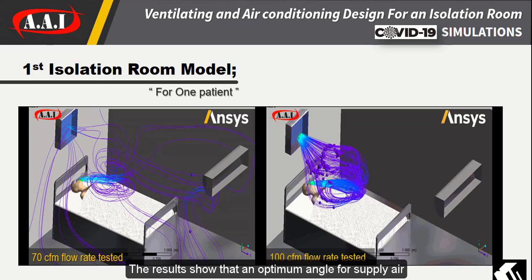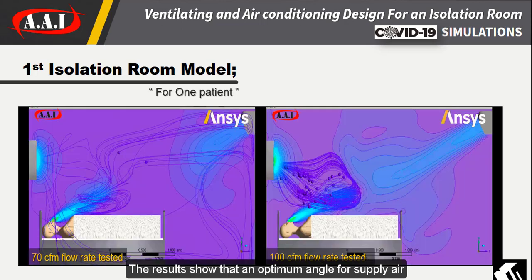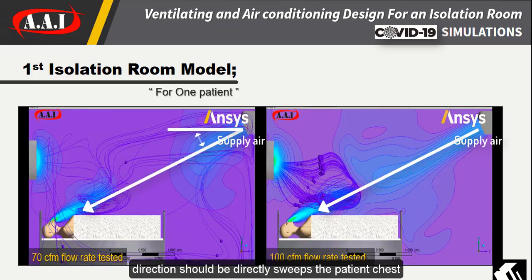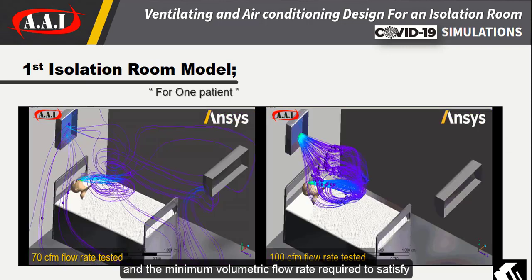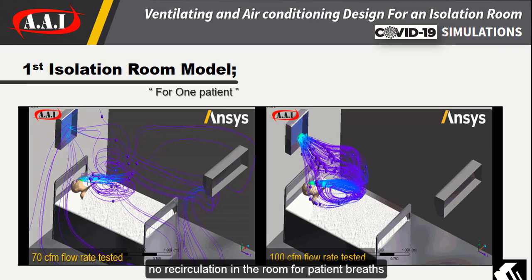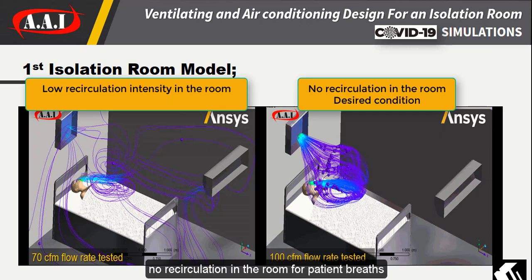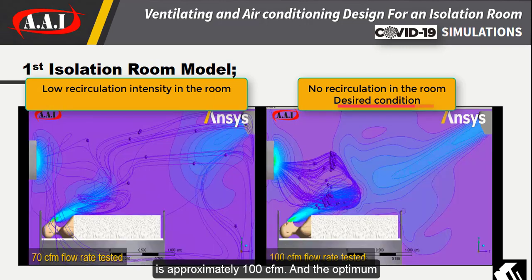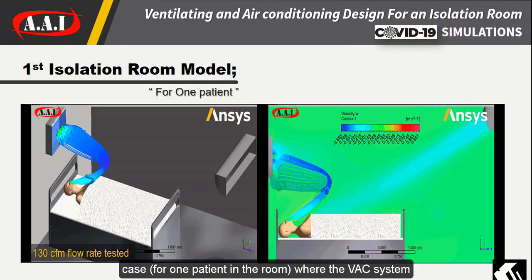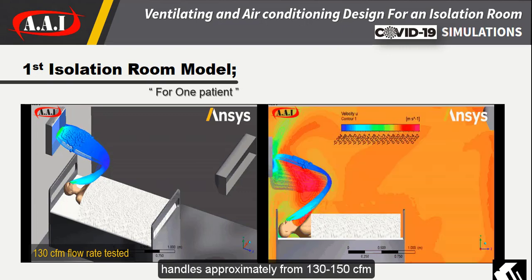The results show that an optimum angle for the supply air direction should directly sweep the patient's chest, and the minimum volumetric flow rate required to satisfy no recirculation in the room for patient breathing is approximately 100 CFM. The optimum case for one patient in the room is where the HVAC system handles approximately 130 to 150 CFM.